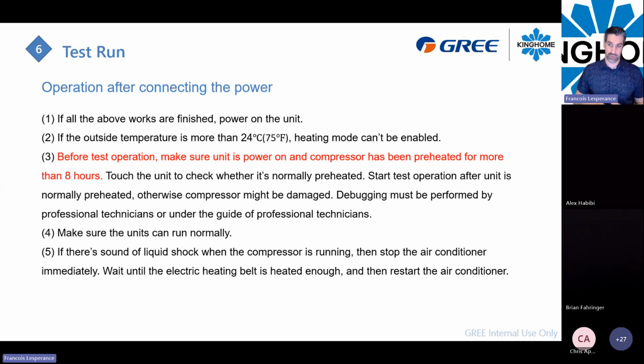Best practice is to apply power to the outdoor unit during your installation. So if the first thing you can do is apply electrical power to the outdoor unit, do that before you do your piping and all the rest, just to make sure the oil inside the compressor will be warmed enough to bring the operation on without breaking the compressor.